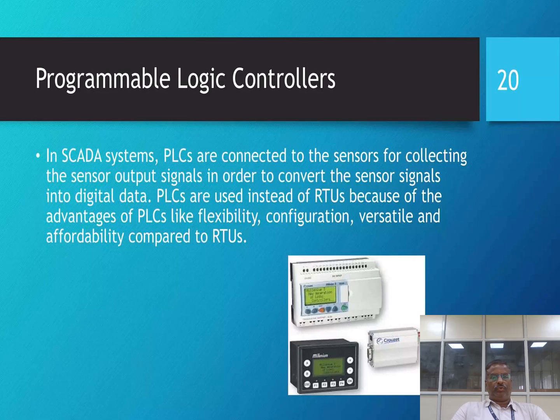In SCADA systems, PLCs are connected to the sensors for collecting the sensor output signals in order to convert the sensor signals into digital data. PLCs are used instead of RTUs because of the advantages of PLCs like flexibility, configuration, versatility, and affordability compared to RTUs, remote terminal units.